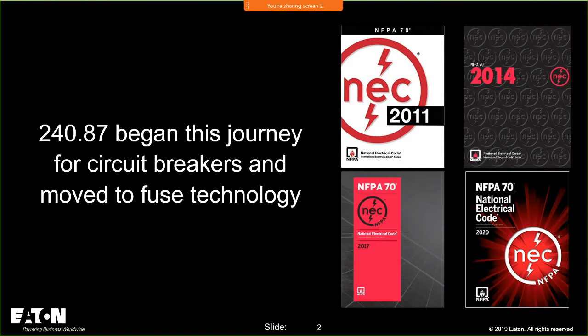240.67. Really, the idea for that began with 240.87. So here's the journey that 240.87 has had, and then it prompted 240.67, because 240.87 is on circuit breakers only. It entered the code in 2011. It's been modified ever since. You know, good code is like a good wine; it gets better with time. But somebody did remind me that if you go too long, wine can turn into vinegar. But the code never turns into vinegar.